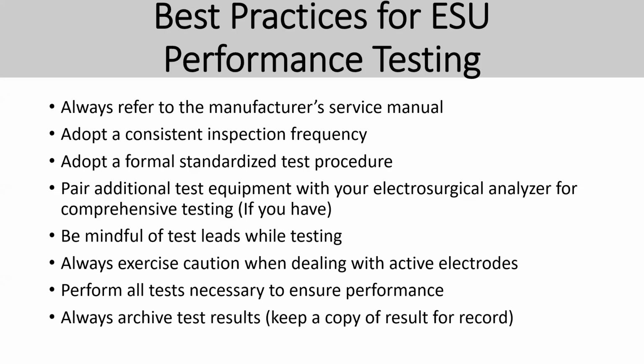Set up a formal standardized test procedure so you can standardize it for all equipment. Pair additional test equipment with your electrosurgical analyzer so you can compare testing if you have one. If you have two electrosurgical analyzers, you can compare the results. If not, it's not necessary.